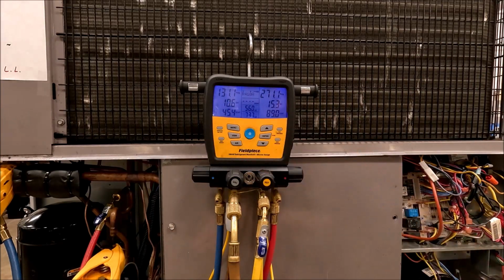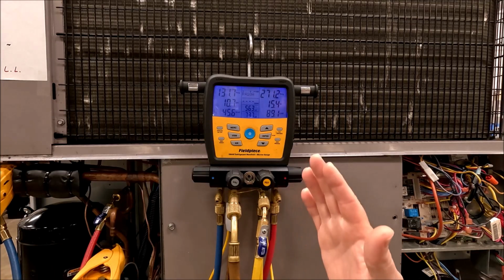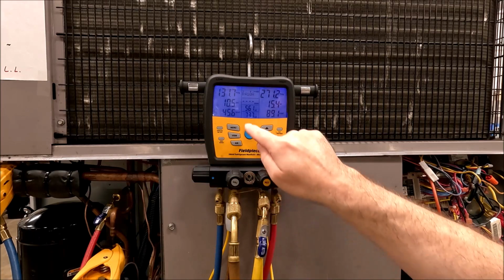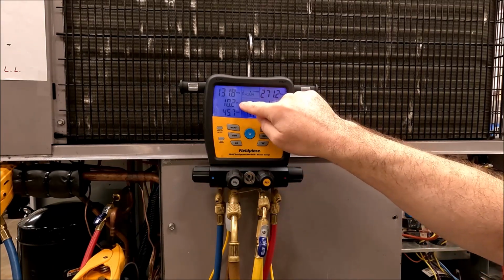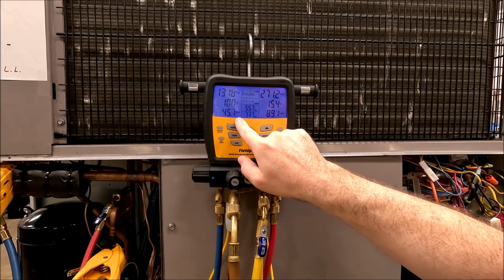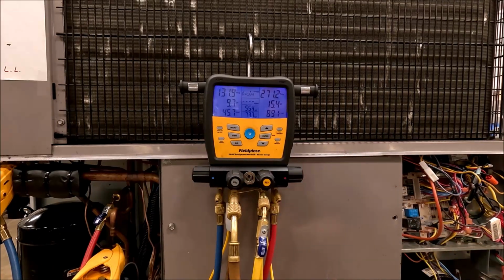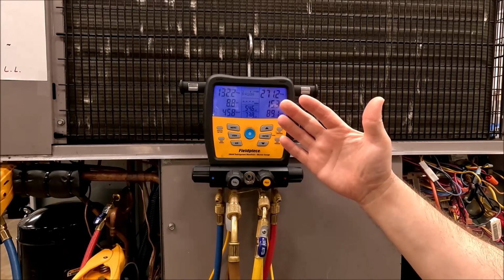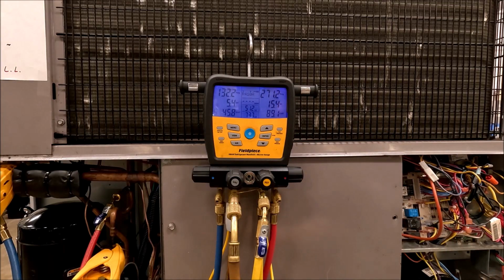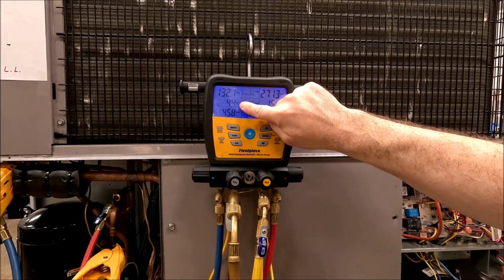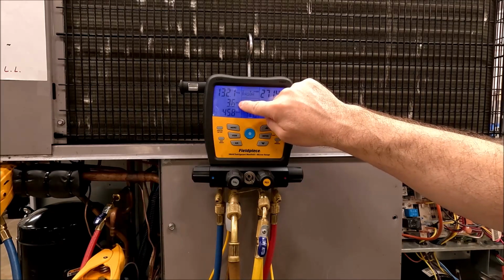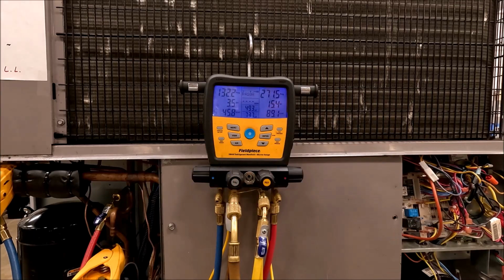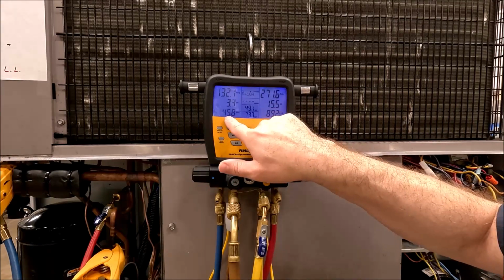So you can tell ours, this TXV is going to open and close, and we've got heat going in and out through the air, through the blower, pulling air across that coil. But you'll watch your superheat move a little bit. You don't see that on analog gauges a lot. All right, you would have to really be good and monitor it. So this is good. So right now, 10 degrees of superheat. If my saturation point is 45.5, 10 degrees higher is my vapor line temperature. So I've got a vapor line about 55 degrees right now, and it's falling. Looks like some of that refrigerant as it's being pulled through by the compressor. I mean, it's falling quite a bit, almost 8 degrees compared to what it did just a second ago. So it was down at 2 degrees superheat. So we're right on the money with this, I believe.